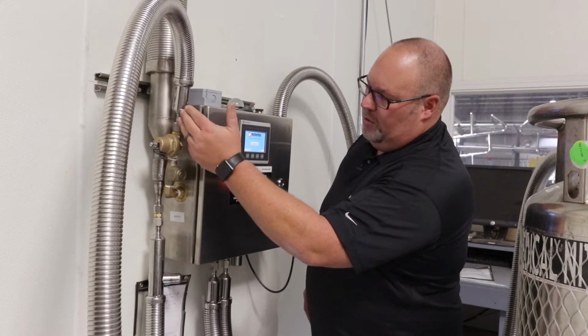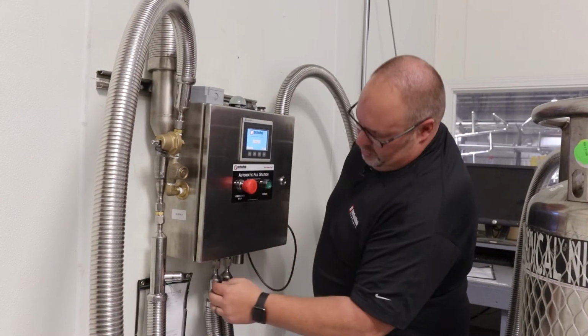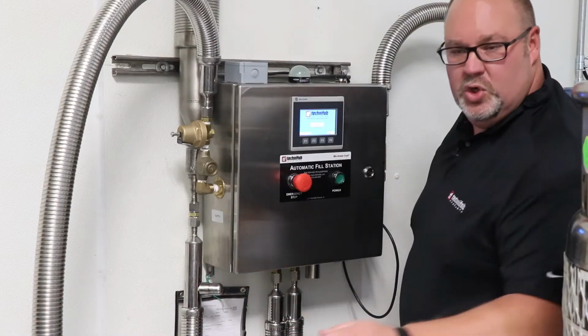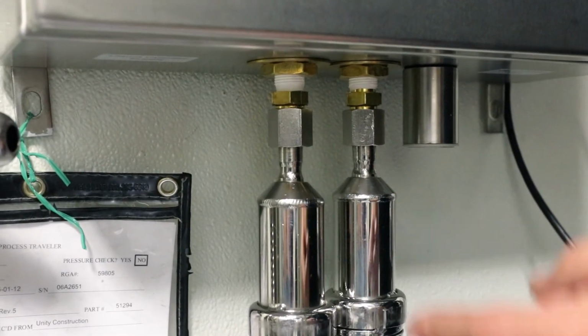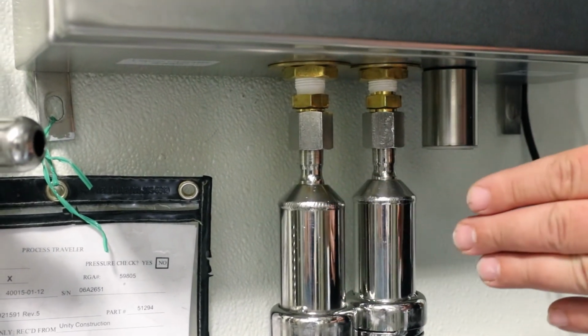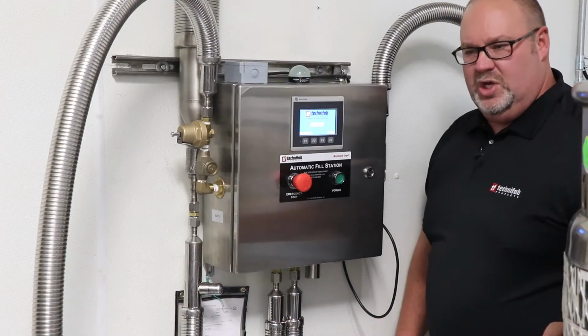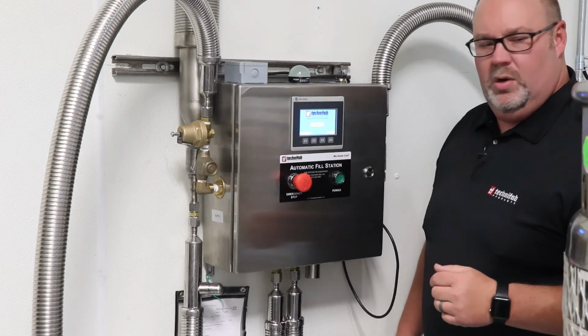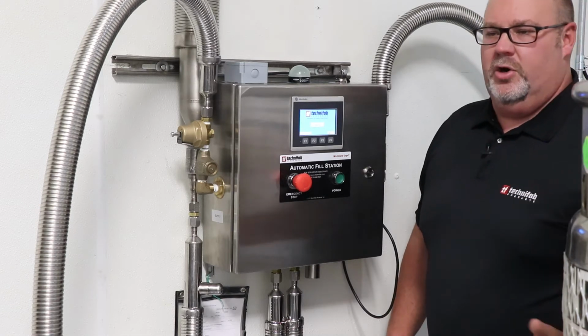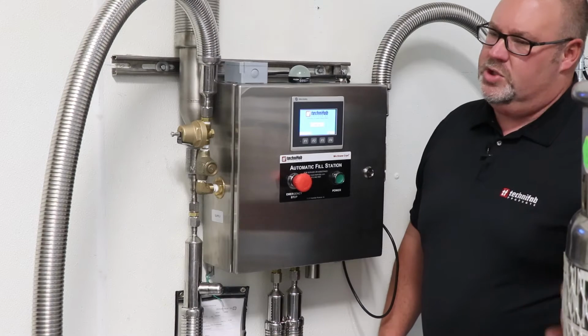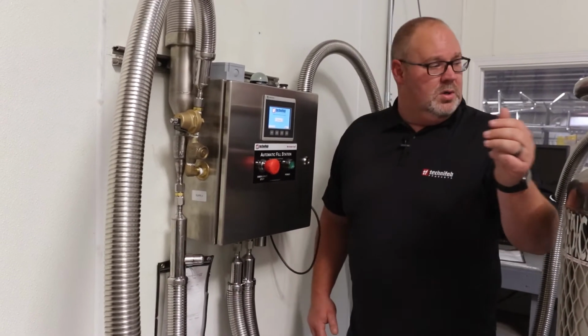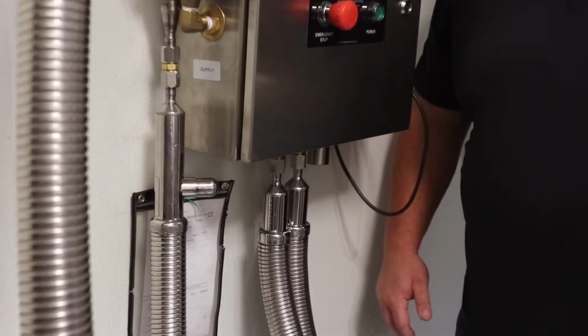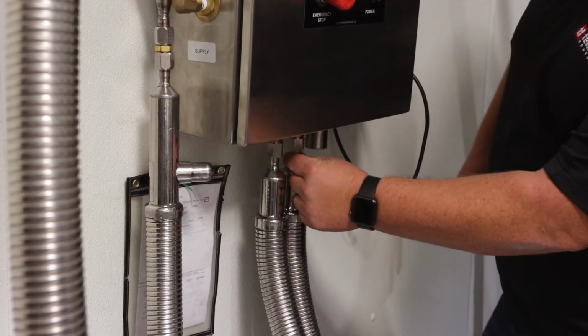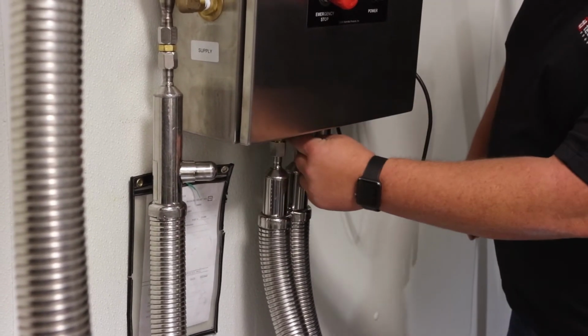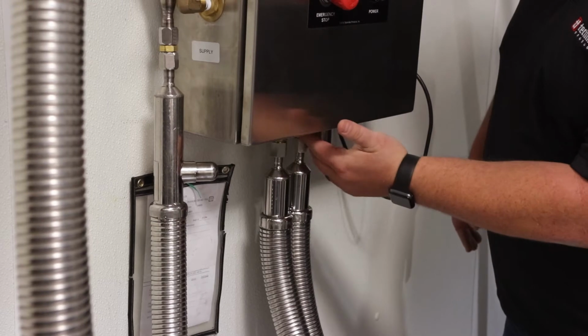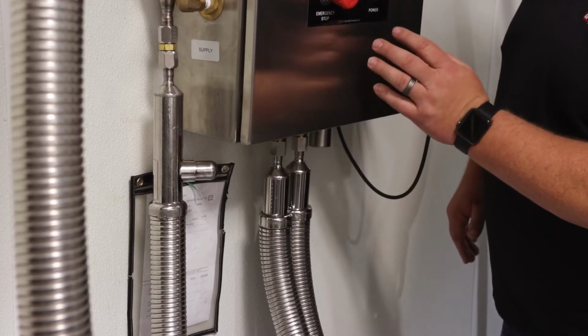So after you have your liquid supply, over here, this is your liquid supply to your VGL. So your liquid will flow through here, in through the unit, out through here to your VGL, which is what this is traditionally used to fill. Also known as a cylinder, 180 liter cylinder, a dewar. From here, you also will have the vent. The vent from the vessel gets returned through this bottom portion connection to the fill station.